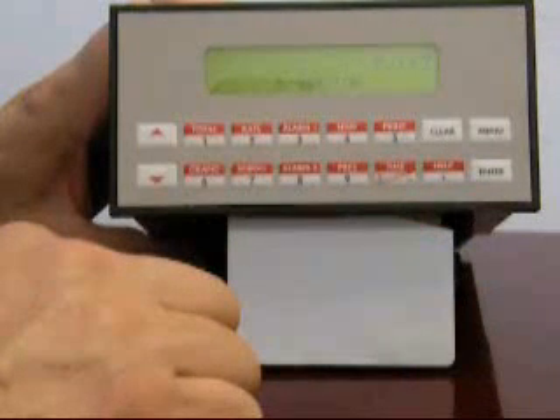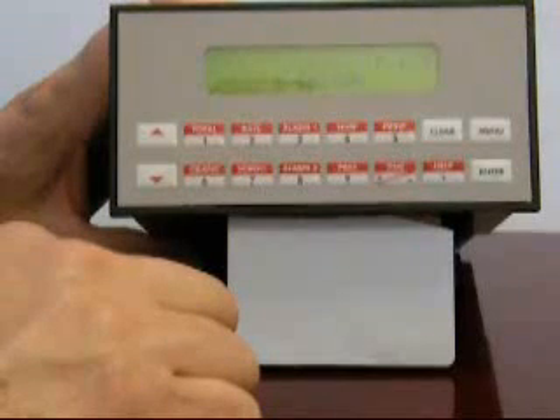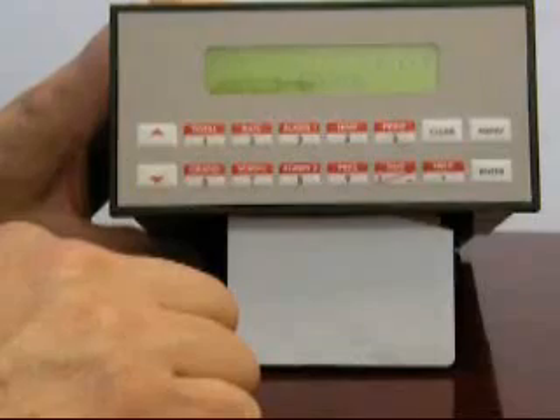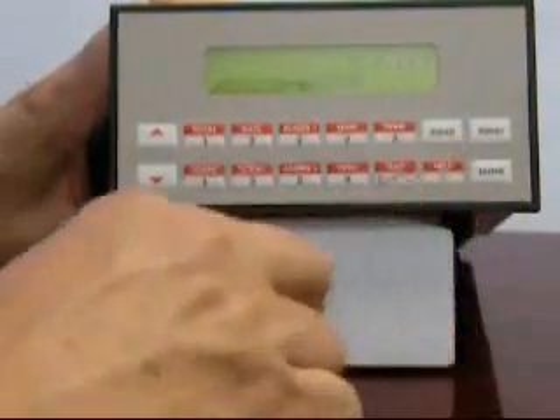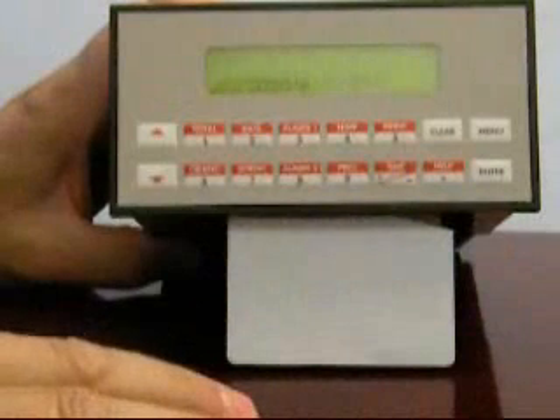You will now see a prompt asking you for the K factor of the flow meter. This number is normally provided by the meter manufacturer, and you'll notice that the instrument is asking you to enter this in pulses per cubic foot. You may find that your flow meter is provided with a calibration in some other unit of measure such as pulses per liter or pulses per gallon, and you would need to convert this to pulses per cubic foot prior to entry. Let's assume our flow meter has a K factor of 200 pulses per cubic foot. To enter a numerical value, press clear followed by the number desired, then press enter.